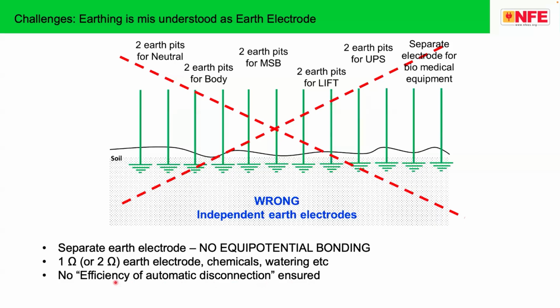Efficiency of automatic disconnection means the tripping time of the device, and how efficiently the device is able to trip is a very important safety measure, which is very, very rarely ensured in hospitals. Recently, I saw a hospital electrical safety audit. The auditor went around the hospital measuring the voltage and current of each panel, then measured the earth pit resistance and made a thermography, and gave to the hospital management saying that your hospital is safe. Then the management told me, look, this is my electrical safety audit report, what is your opinion? I replied to them that whatever is written, voltage, current, earth pit resistance and thermography, all these are not related to electrical safety.